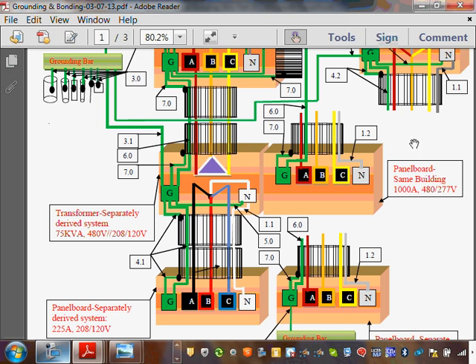Primary is delta. These are separately derived systems. The reason they call them separately derived systems is, I want you to focus on the delta and the Y. Don't look at the green. Just look at the other colors other than green. Is there any physical, mechanical connection between the delta and the Y? So complete separation, right? That's the definition of a separately derived system. No connection whatsoever between the primary and the secondary.